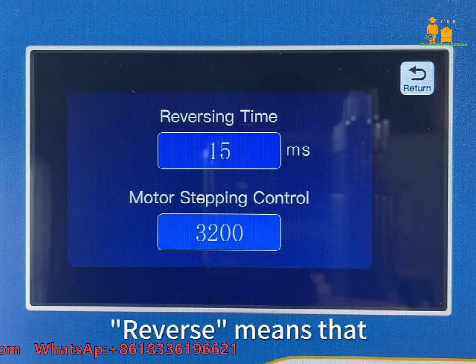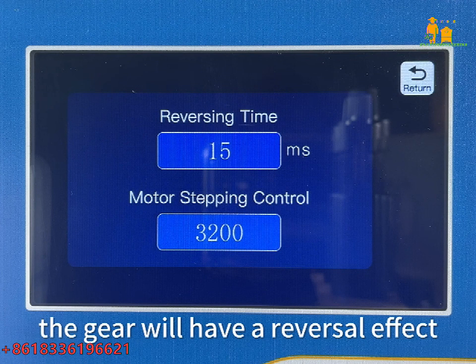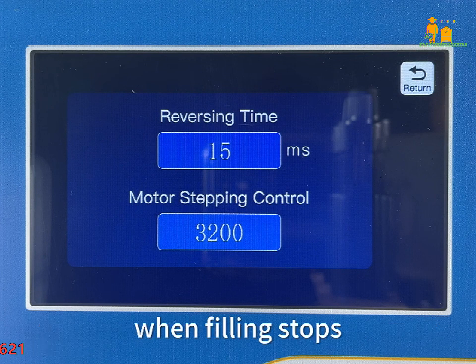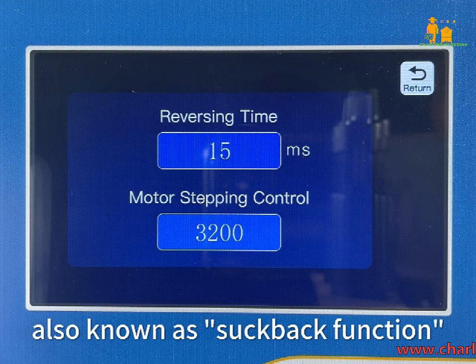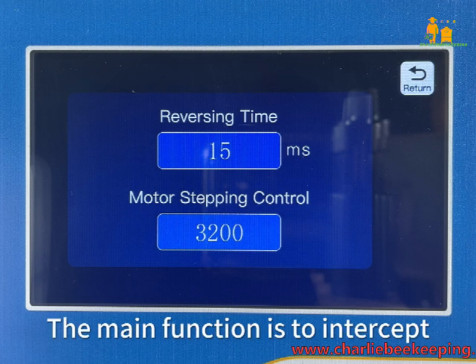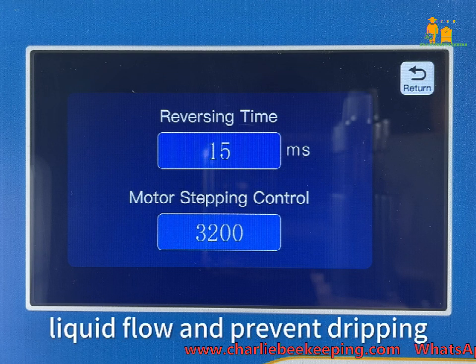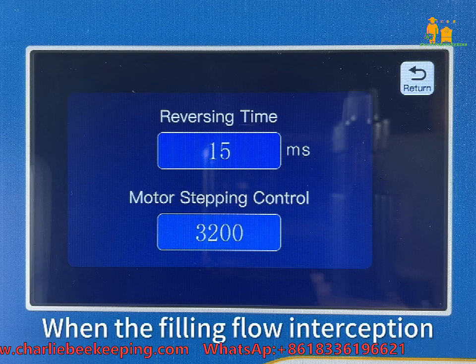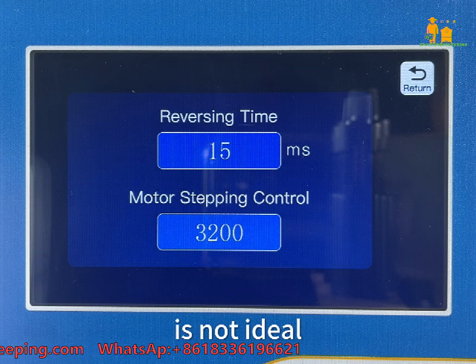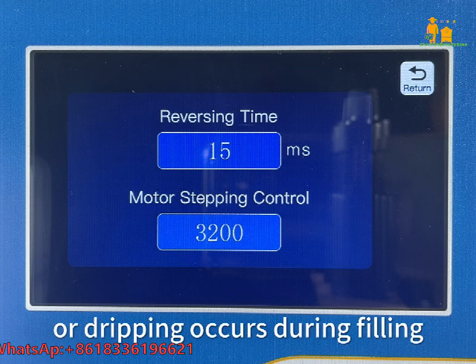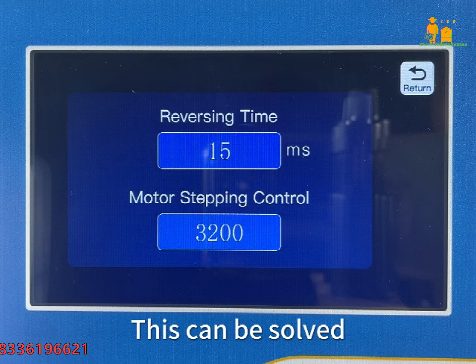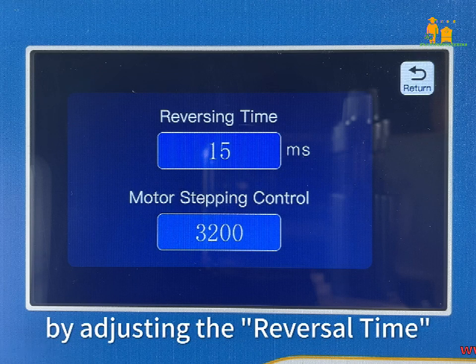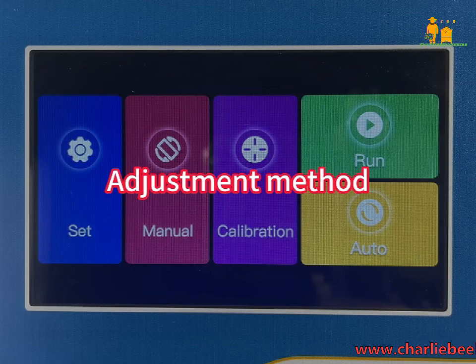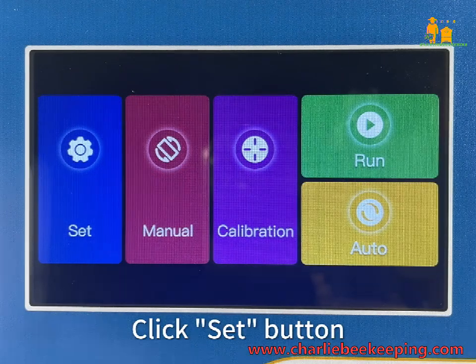Reverse time adjustment. Reverse means that the gear will have a reversal effect when filling stops, also known as suckback function. The main function is to intercept liquid flow and prevent dripping. When the filling flow interception is not ideal or dripping occurs during filling, this can be solved by adjusting the reversal time. Adjustment method. Click Set button.